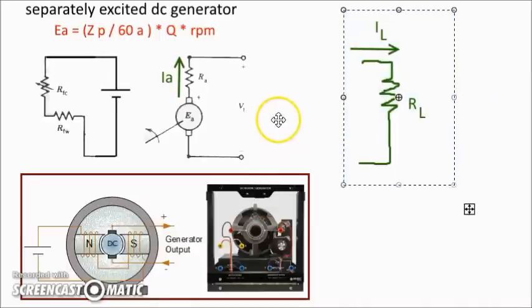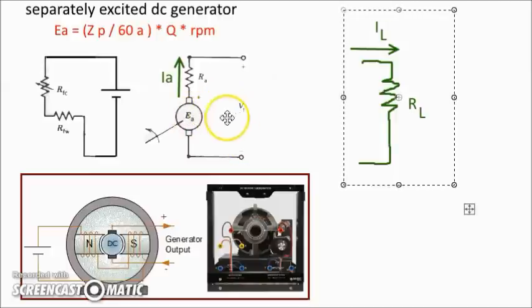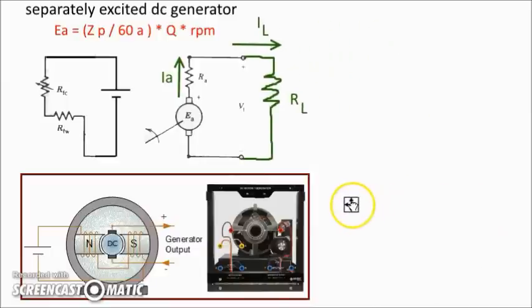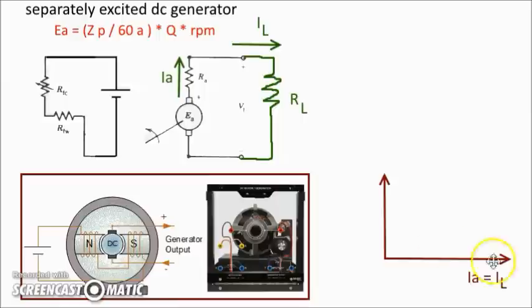The first measurement we did in lab three was the open circuit measurement. When the generator is open circuit, the armature current is zero. When armature current is zero, the terminal voltage Vt and Ea are the same, so we can measure Ea by simply measuring terminal voltage. After this, we connected the load to the terminal. In a separately excited DC generator, the load current and armature current are the same because they are in series, so Ia and IL are equal.